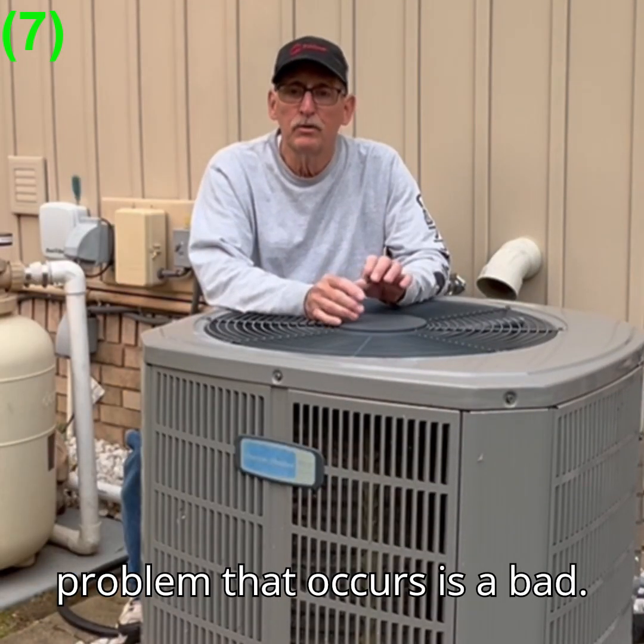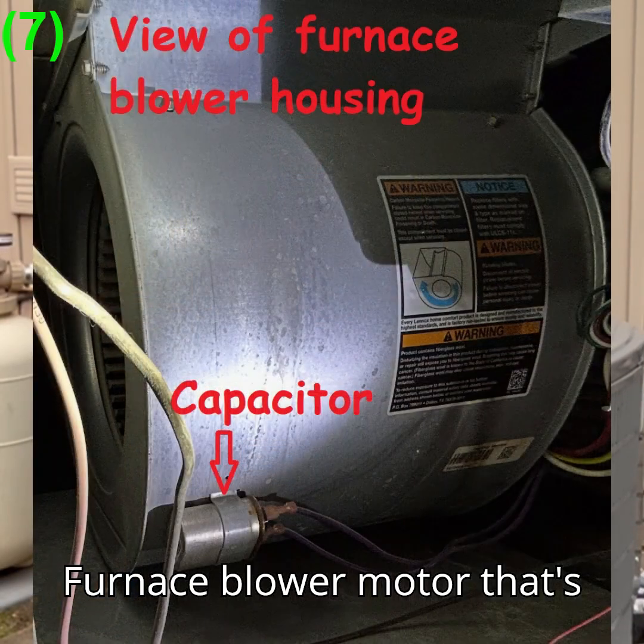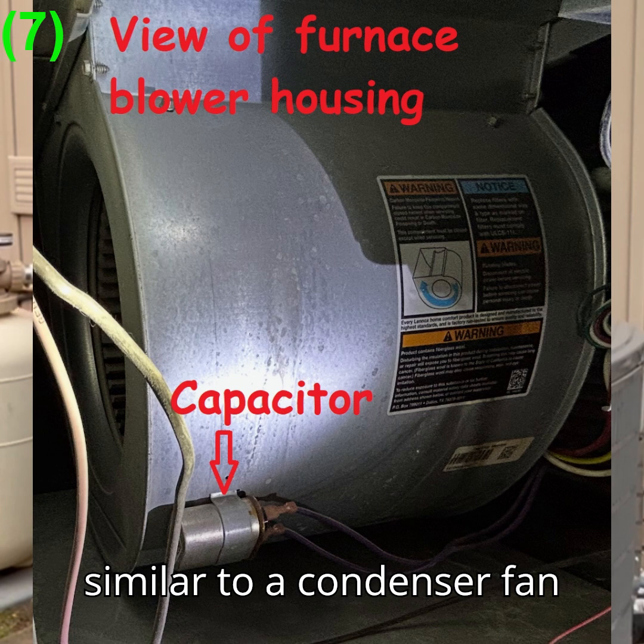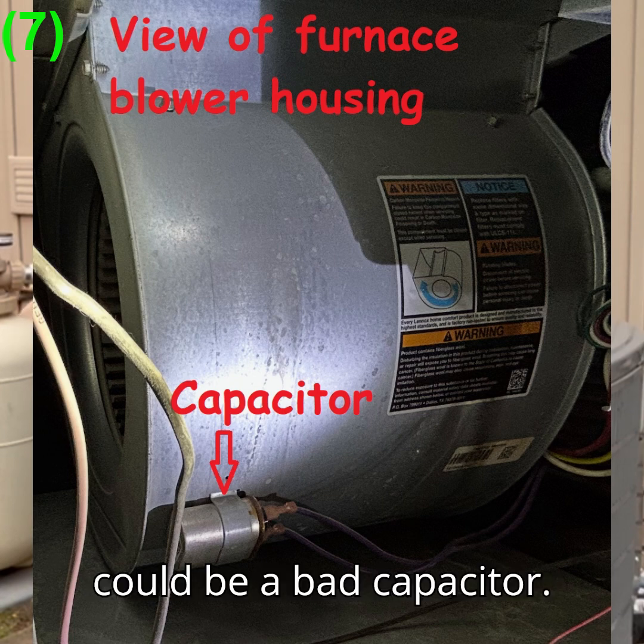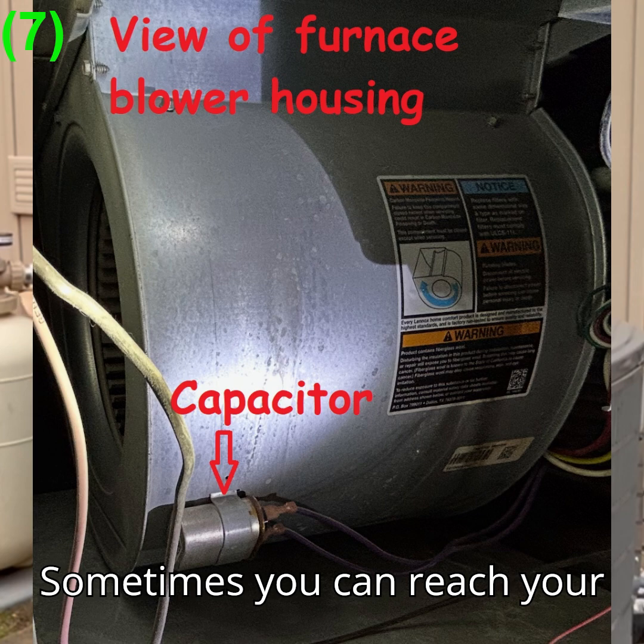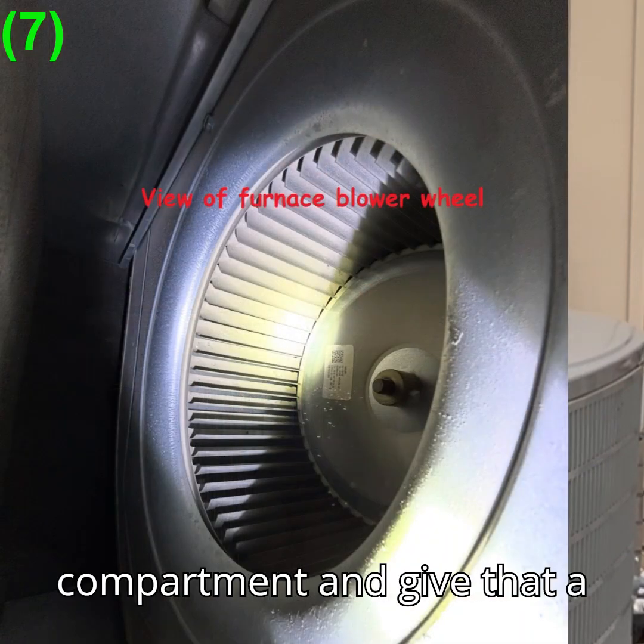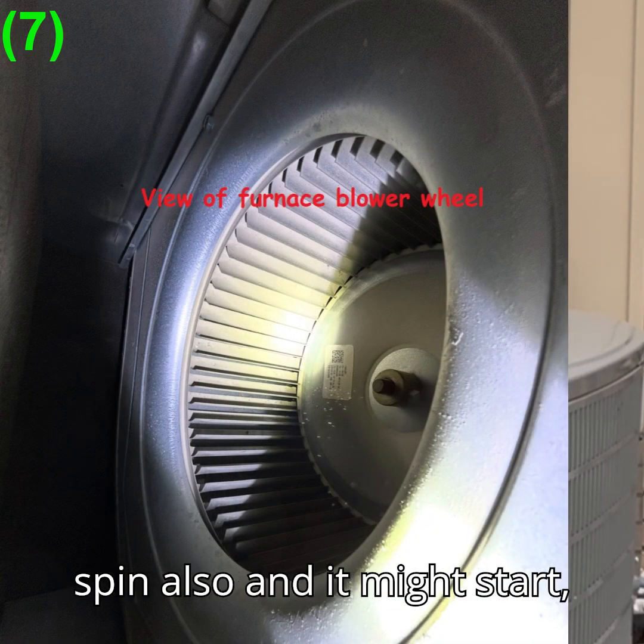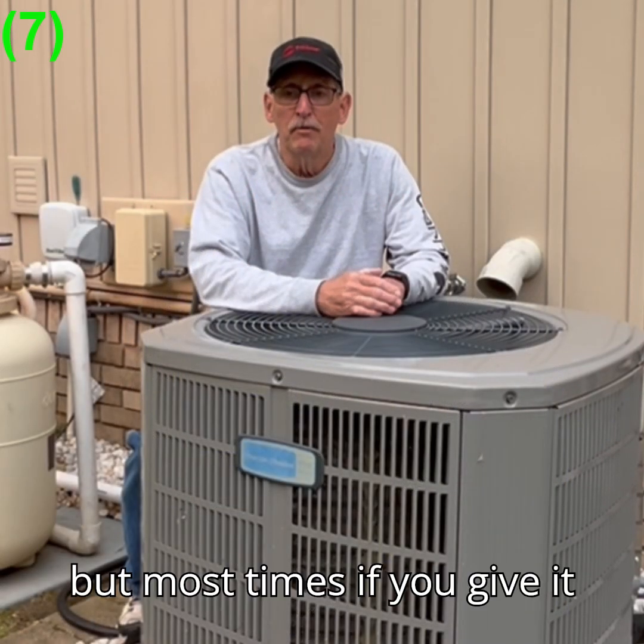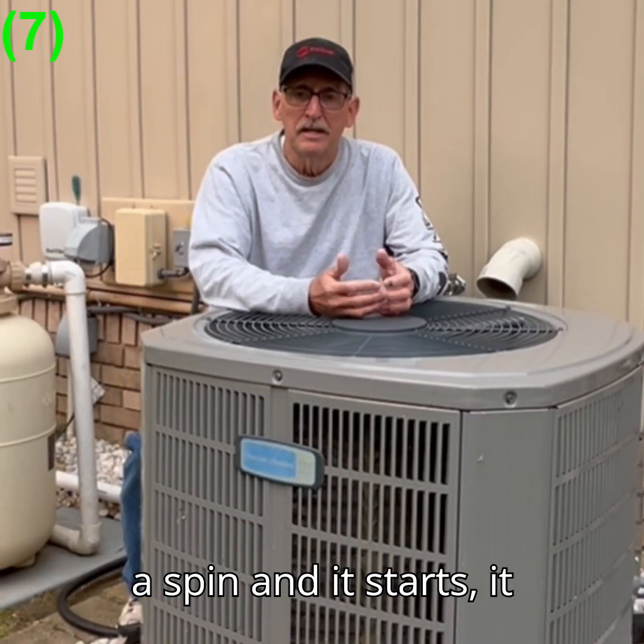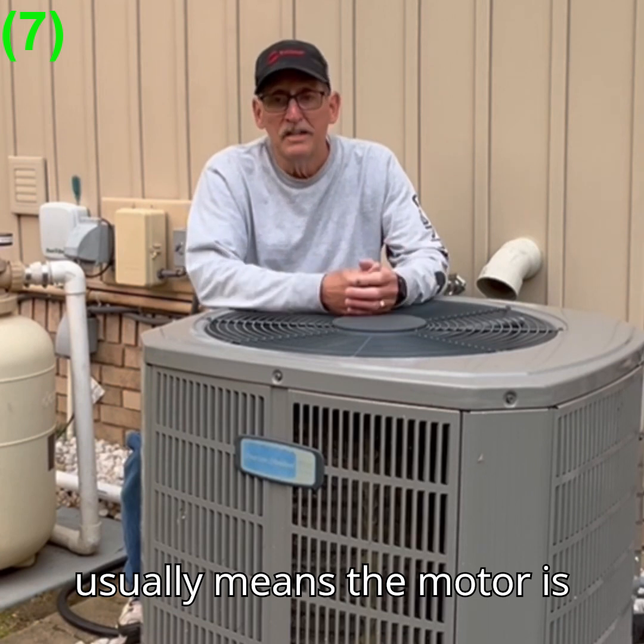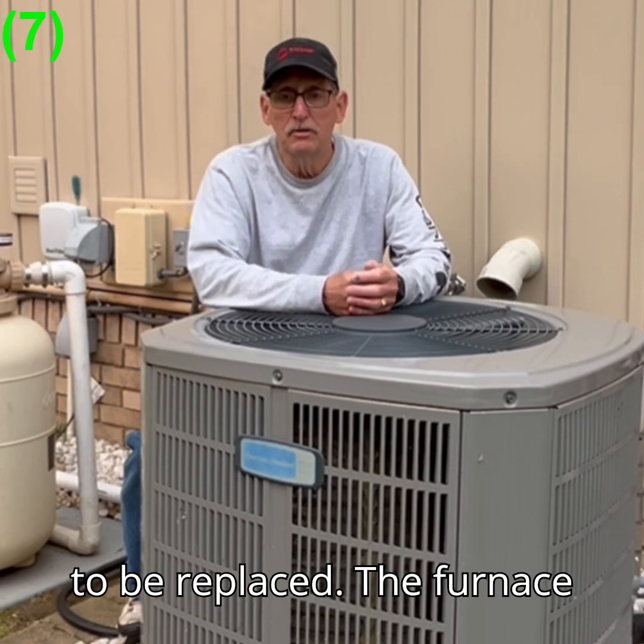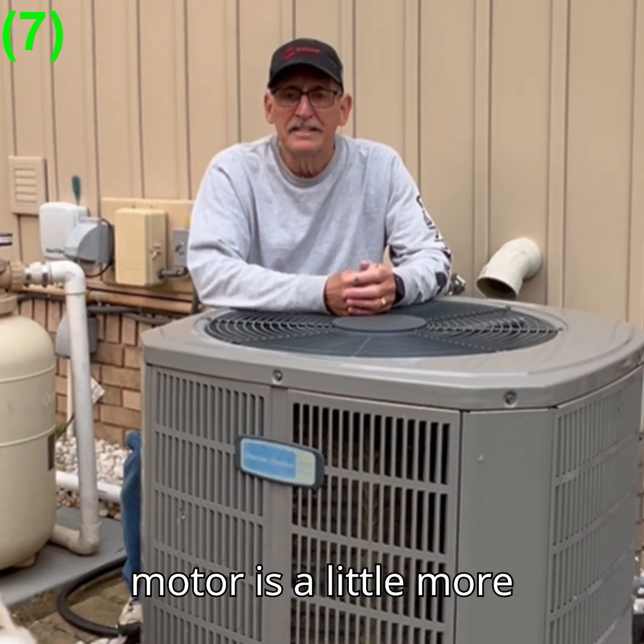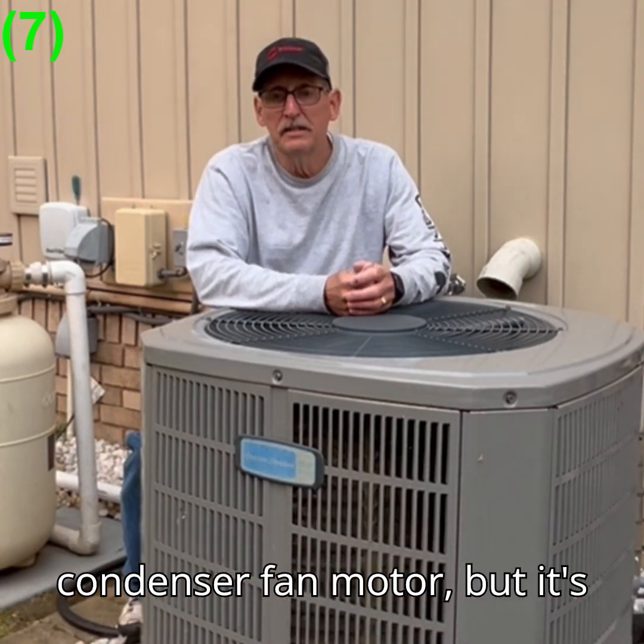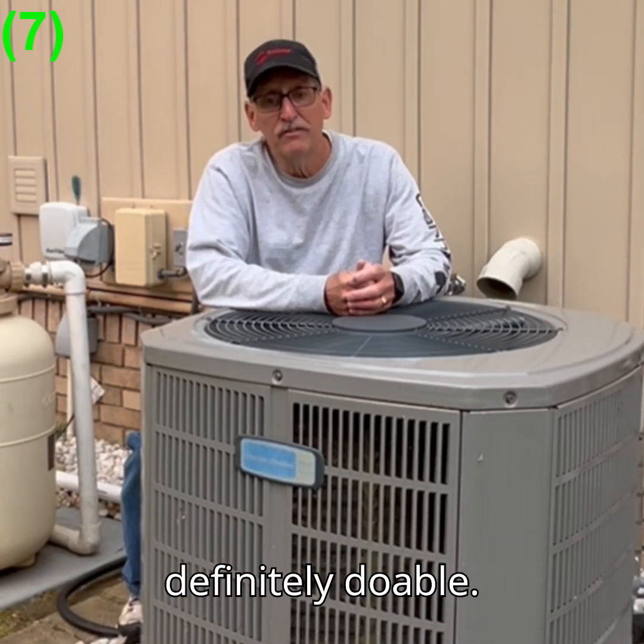Another problem that occurs is a bad furnace blower motor. That's similar to a condenser fan motor in the respect that it could be a bad capacitor. Sometimes you can reach your hand in the blower compartment and give that a spin also, and it might start. But most times, if you give it a spin and it starts, it usually means the motor is going to fail again and needs to be replaced. The furnace motor is a little more difficult to replace than the condenser fan motor, but it's definitely doable.